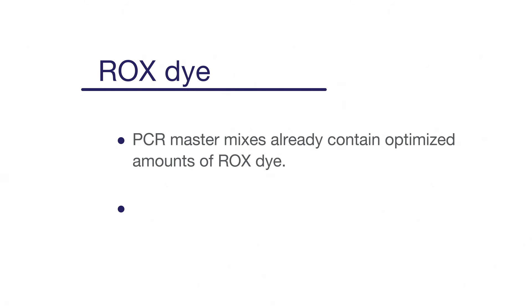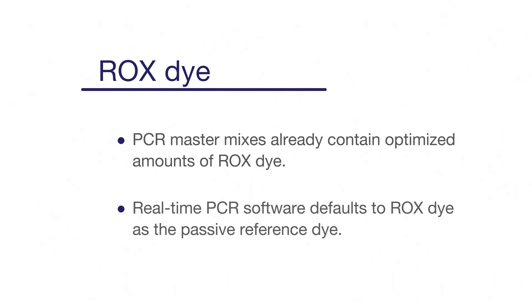There are two key points to mention about ROX. With a couple of exceptions, Applied Biosystems' real-time PCR mastermixes already contain optimized amounts of ROX when they arrive at your door, so there's no need to add it. Second, Applied Biosystems' real-time PCR software defaults to ROX as the passive reference dye. This is important to know, because if for some reason you decide to use a mastermix that doesn't contain ROX, you'll want to change the passive reference dye selection to none.